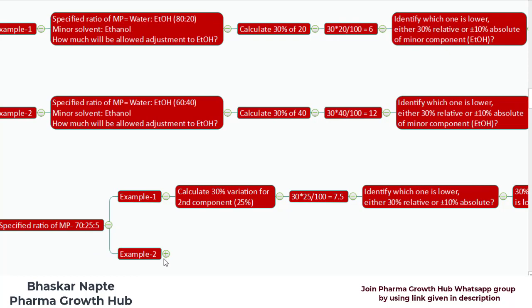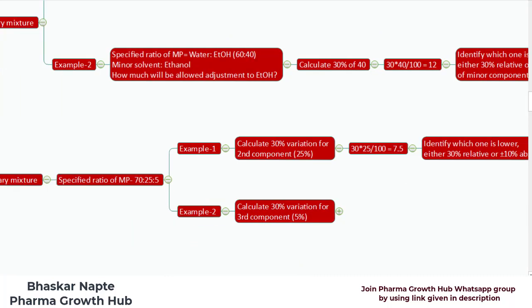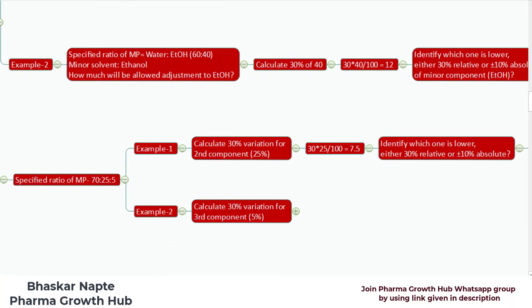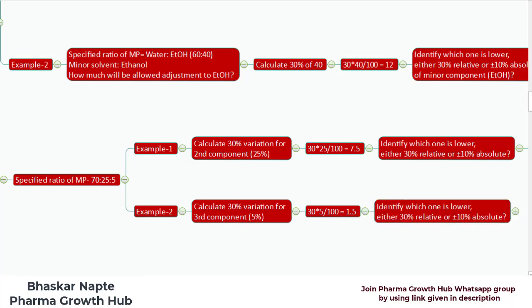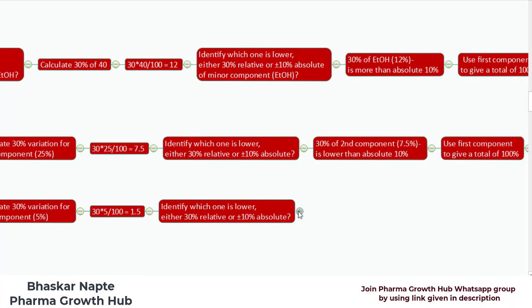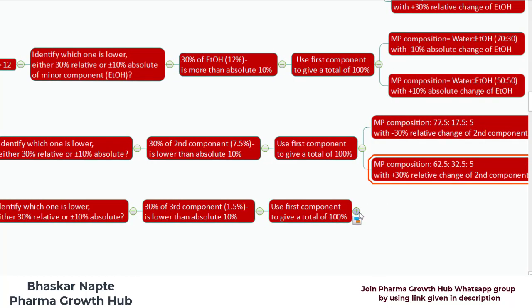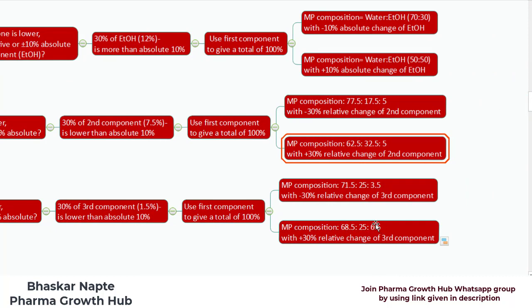Let us talk about example number 2, where I am going to change the third component. Calculate the 30% variation for the third component, which is 5% in the given example. The 30% of 5 becomes 1.5. Identify which one is lower — the 30% of this third compound is 1.5%, which is much lower than 10%. So I am going to use the 30% variation. Use the first component to give a total of 100%, and these are the allowable variations.